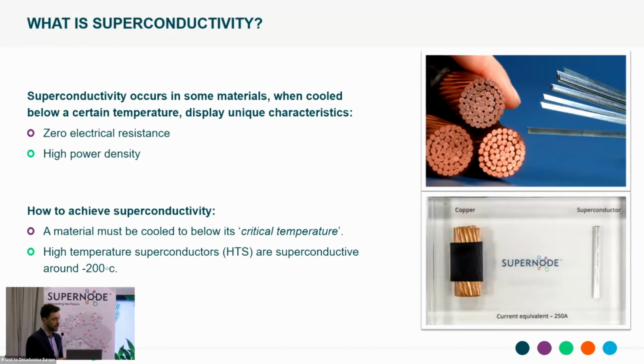In superconducting power cables, we generally use liquid nitrogen as the coolant. We cool them down to minus 200 degrees, and then we can operate them in a very power dense way. The superconducting material is normally manufactured into tapes, shown in the image on the right. The tapes are combined together and wound into a cable, pretty much like a copper cable. That's how you get a power cable made from superconductors.